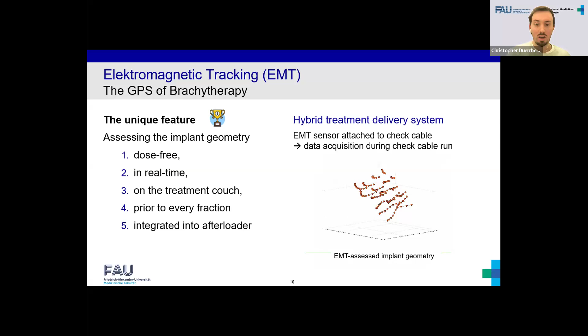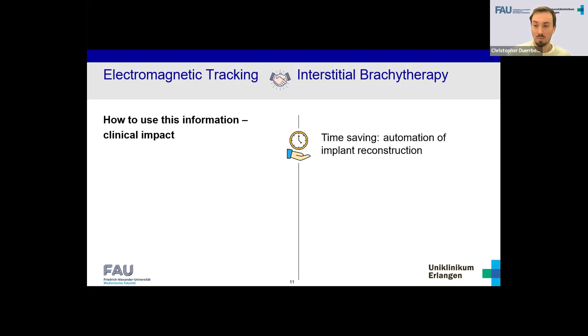Now, we can use this EMT-assessed implant geometry for various purposes. And first of all, we can save quite a lot of time because this implant reconstruction, so the clinical step that you would perform based on a CT for treatment planning, takes quite a lot of time, at least in breast brachytherapy, because we usually have between 15 and 25 catheters. And for each of them, you require 2 to 3 minutes to reconstruct them. So you end up with 45 to 60 minutes for very large implants, even more than that. And that's really time that you could save doing that automatically with this system.